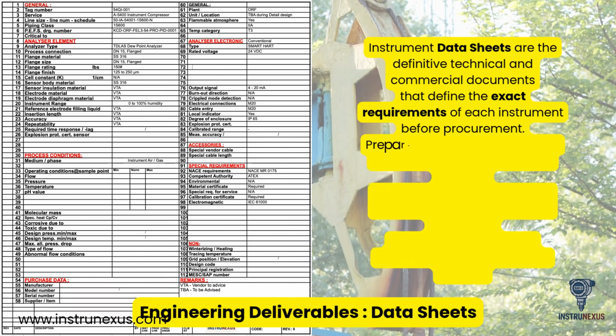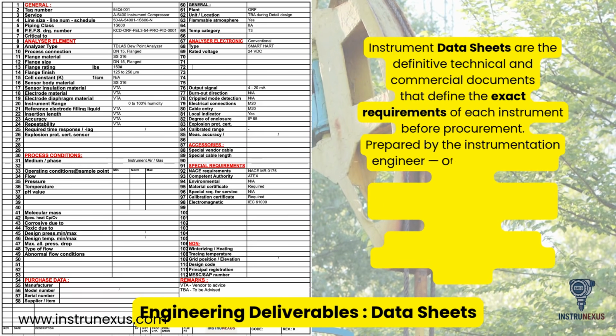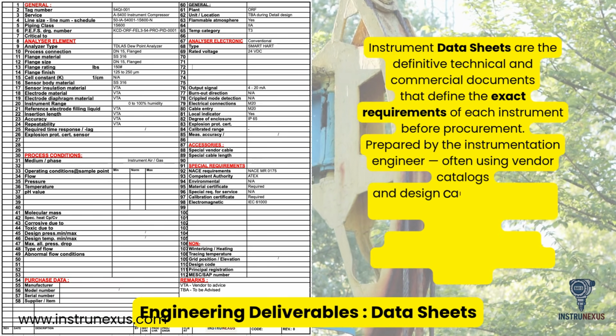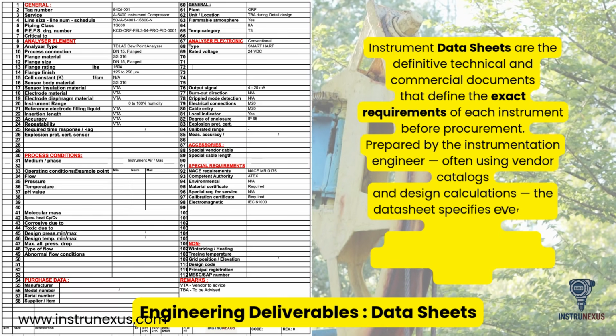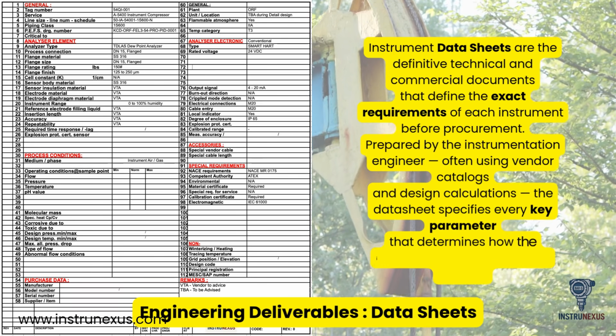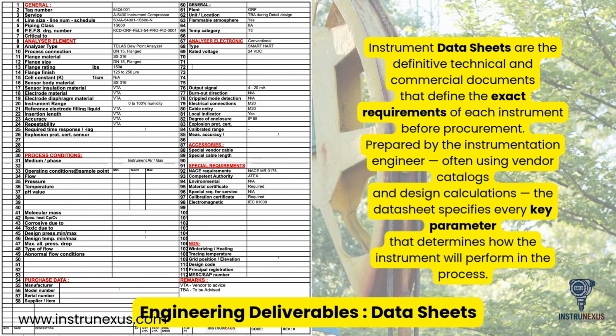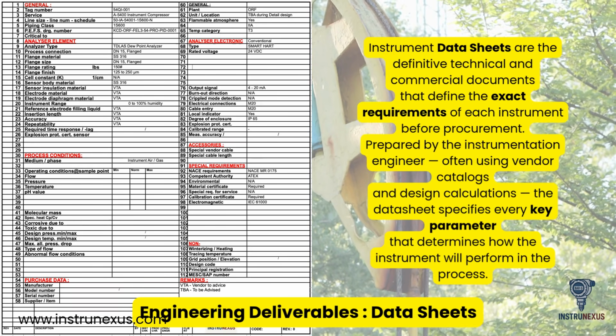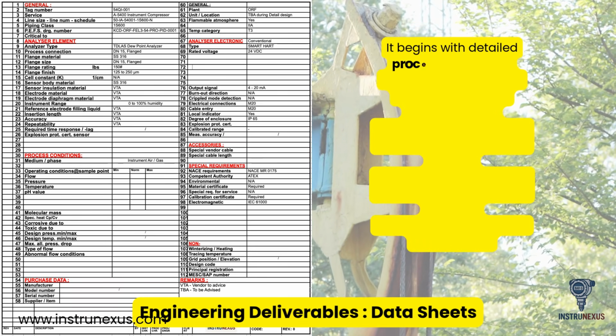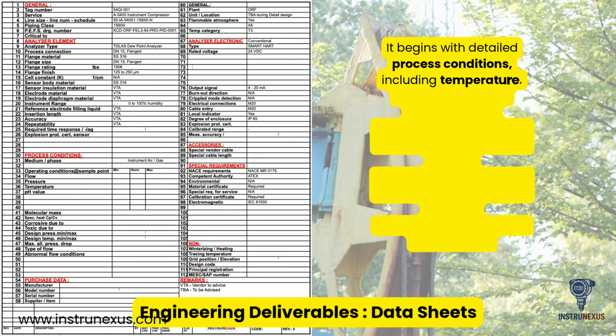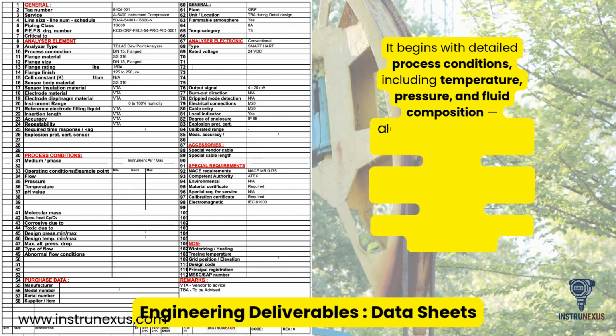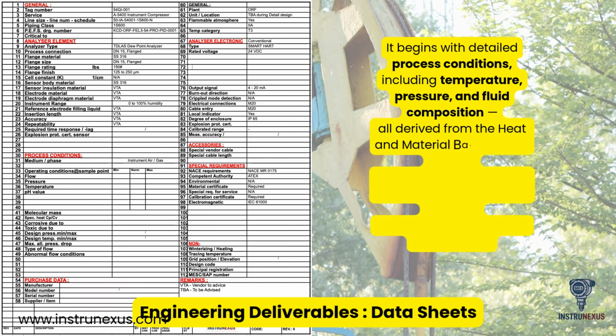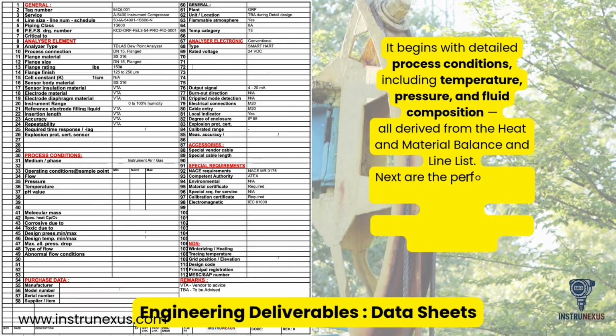Instrument datasheets are the definitive technical and commercial documents that define the exact requirements of each instrument before procurement. Prepared by the instrumentation engineer, often using vendor catalogs and design calculations, the datasheet specifies every key parameter that determines how the instrument will perform in the process. It begins with detailed process conditions, including temperature, pressure, and fluid composition, all derived from the heat and material balance and line list.